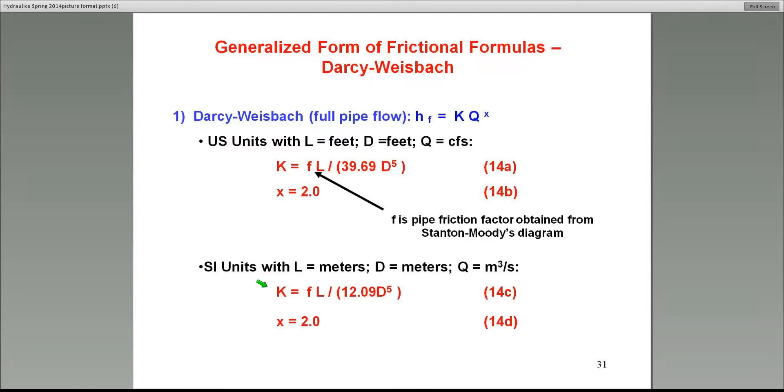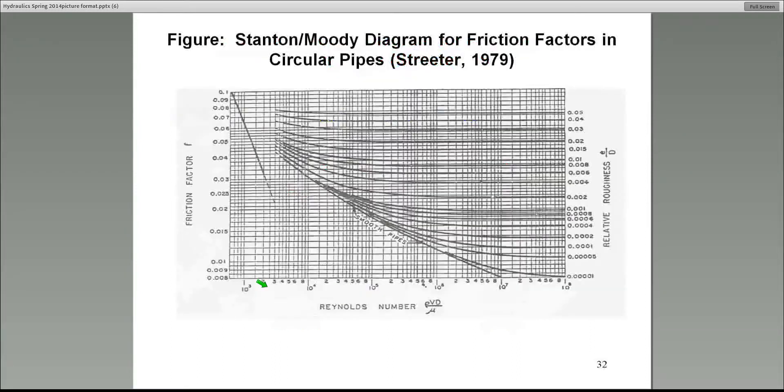Here's the K for SI units. On the next slide is the Hazen-Williams, and I'll use that and I'll show you that in a minute. But here's the Moody and Stanton-Moody's diagram that we talked about. There's a friction factor f, Reynolds number, and of course, the relative roughness. If you're using the Darcy-Weisbach method, you've got to get familiar with this diagram.